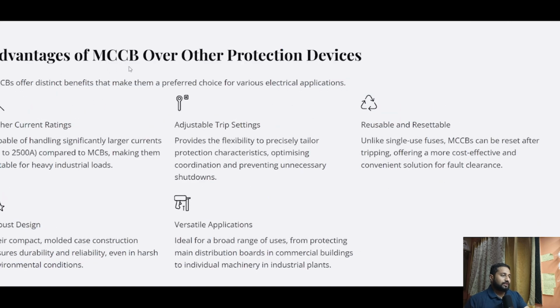So what are the advantages of MCCBs over other protection devices? MCCBs offer distinct benefits that make them a preferred choice for various electrical applications. First would be higher current ratings. As we have discussed, they are capable of handling significantly larger currents, up to the value of 2500 amperes, compared to MCBs, making them suitable for heavy industrial loads. And it has adjustable trip settings, which provide flexibility to precisely tailor protection characteristics, optimizing coordination and preventing unnecessary shutdowns.